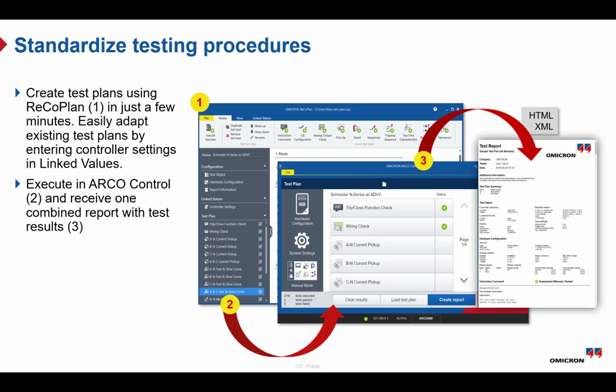Now let's look at how to standardize testing procedures using ReCoPlan. ReCoPlan is a PC-based software used to create and manage test plans for Recloser and Sectionalizer testing. You can either create a new test plan or open an existing one. When creating a new plan, you select the manufacturer, choose the controller adapters, and then add the required test tools. After that, you simply enter the test values. If you are using an existing plan, you can easily adapt it by adapting the controller setting using linked values.